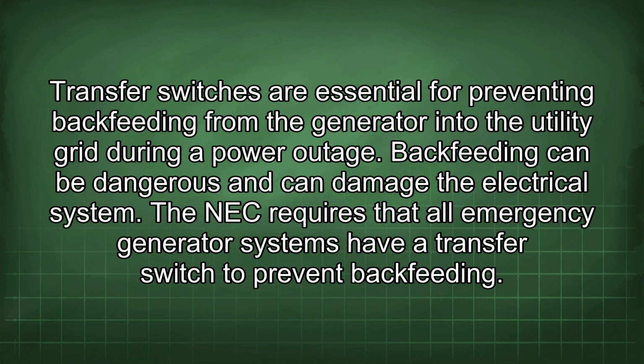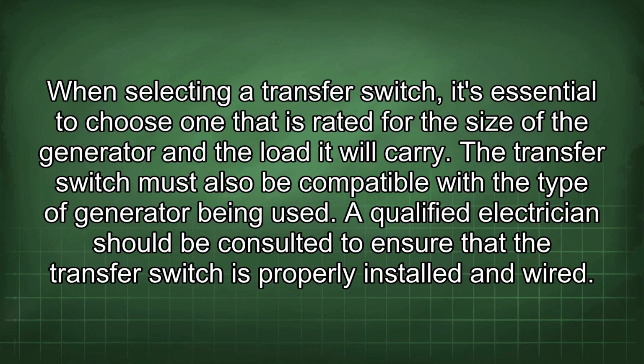Transfer switches are essential for preventing backfeeding from the generator into the utility grid during a power outage. Backfeeding can be dangerous and can damage the electrical system. The NEC requires that all emergency generator systems have a transfer switch to prevent backfeeding. When selecting a transfer switch, it's essential to choose one that is rated for the size of the generator and the load it will carry. The transfer switch must also be compatible with the type of generator being used. A qualified electrician should be consulted to ensure that the transfer switch is properly installed and wired.